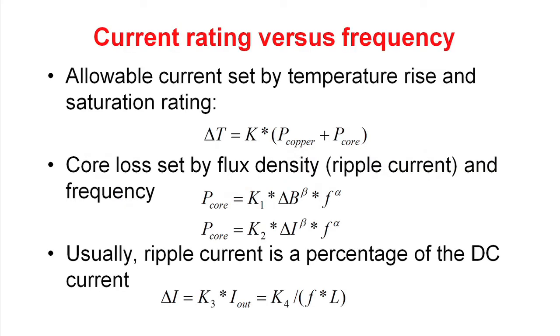Here are a number of equations that tell you the characteristics of an inductor. As in all magnetics, the size of the inductor is set by the temperature rise normally and then maybe by the saturation rating of the core material. We can calculate the temperature rise of the inductor as some constant times the sum of the copper loss and the core loss. And the core loss is set by the flux density in the inductor and the operating frequency.